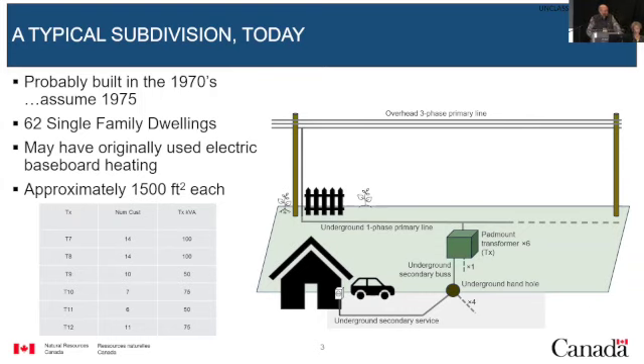Now let's talk about what's going to be needed when we electrify that subdivision. It was built in the 1970s, people live there and will continue to for years. The 3-phase overhead line we probably won't touch, but we'll have to rebuild the single-phase underground primary, which was put in the 1970s and is direct buried—meaning no duct, so if you want to replace the cable, you dig it up. There are 6 pad-mount transformers, and we're going to increase that to about 10 based on electric vehicles, home electrification, and getting rid of gas heat.